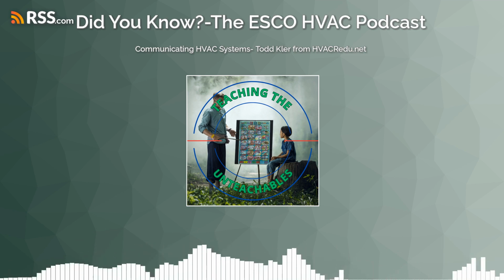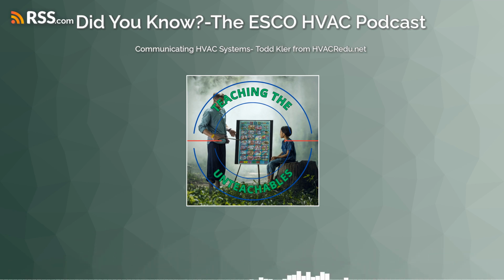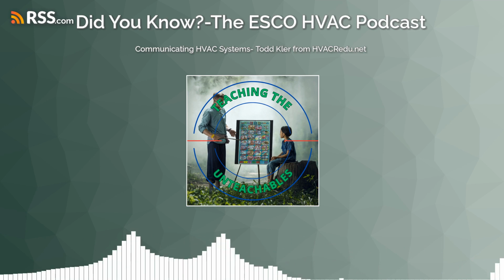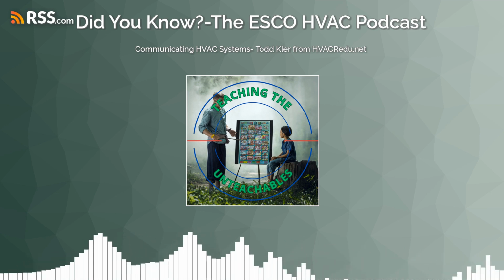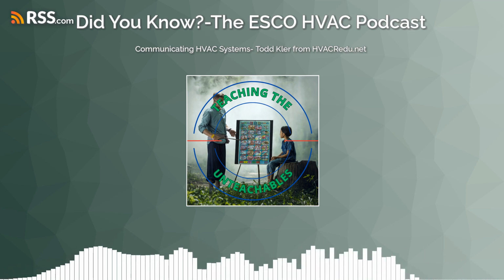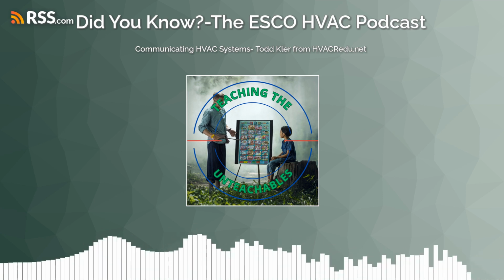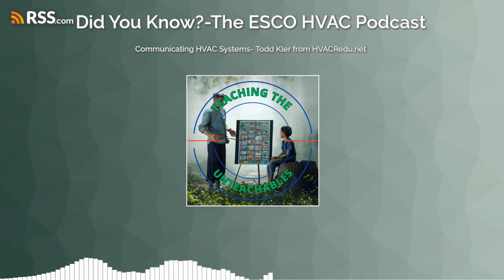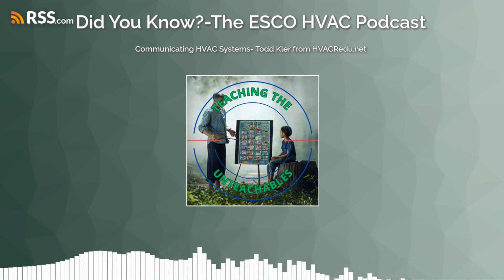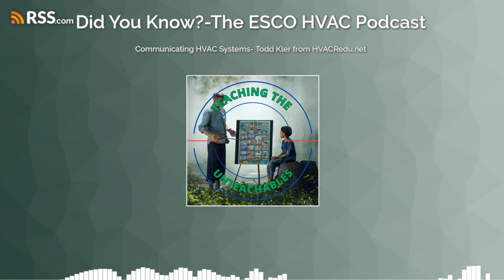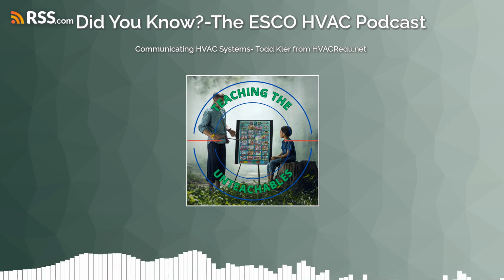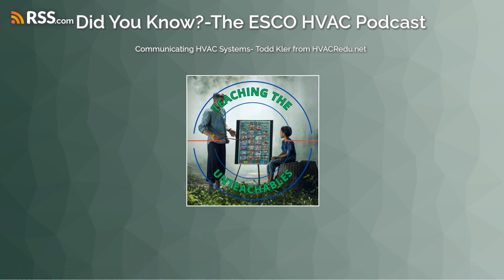Let's just keep on going. And anything outside those parameters, we got a problem. You got a problem between them. It's typically your wiring. Absolutely. It's usually not the controller. It's usually not the board. Yep. The only thing that I don't see in many of these, except for the very first one, is a measurement between A and B, which would be our bias voltage. So I need to round up some. I need to get in some of my friends' labs and ask, what's the bias voltage on every one of these manufacturers? Because I got a feeling they all operate under the same principle: if I have a certain bias and it's below this, I can't communicate well.